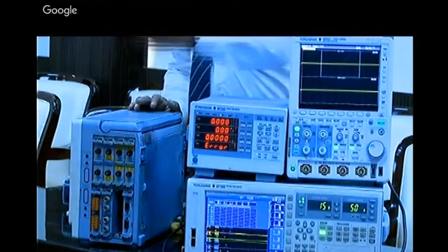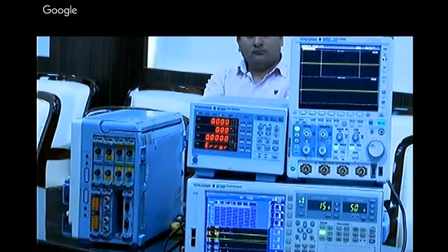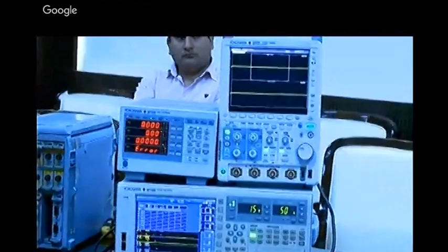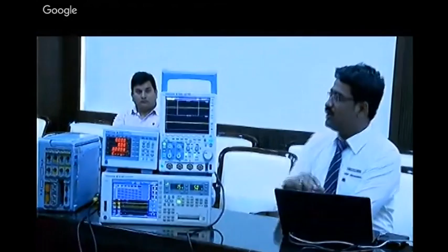It's having up to 128 channels and a 100 megasamples module. Logic channels can also be put in, with best noise immunity—it will suppress the surrounding noise. And there's backward compatibility: earlier we had the DL750 before coming to the DL850, and those modules can also be used in this one.